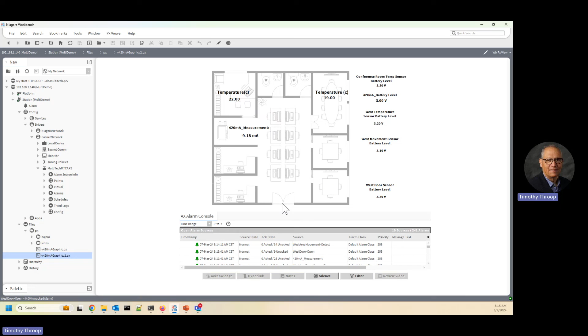So there are a lot of different ways you can display these alarms, but the whole point here is that these wireless sensors can add a lot of value to an existing building management system. Most building management systems may only contain temperature, pressure, and air quality sensors, and those are all very important. But if you want to add additional monitoring capability, rather than going through the whole wiring process, you can simply deploy these sensors wirelessly, put them just about anywhere, and gather more data. Then based on that data, have the building management system take some sort of action.